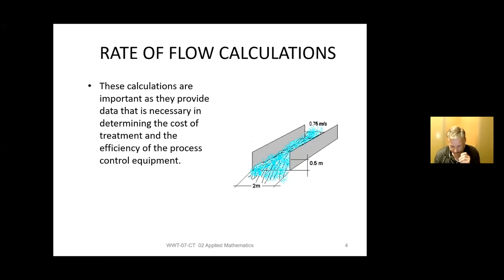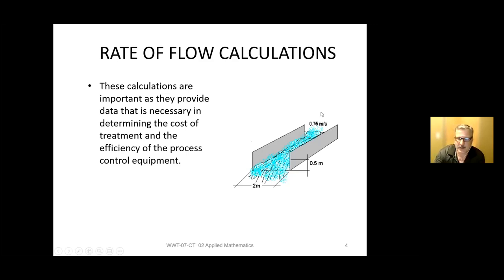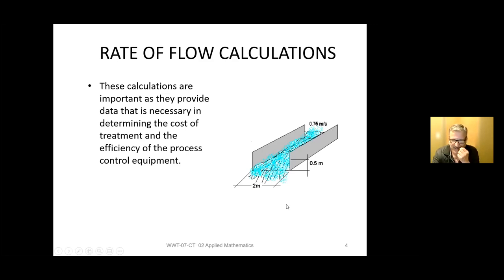Rate of flow calculations are used a lot — for testing flow meters, pumping capabilities, and figuring out how much flow you can put through a tank. We'll cover a rectangular channel example and then a pipe example. In this channel question: the channel is 2 meters wide, the depth is 0.5 meters, and it's flowing at 0.75 meters per second — all in meters, so no conversions needed. The question asks for daily flow in the channel if the velocity is 0.75 meters per second. Read questions closely because the required answer is in daily flow.